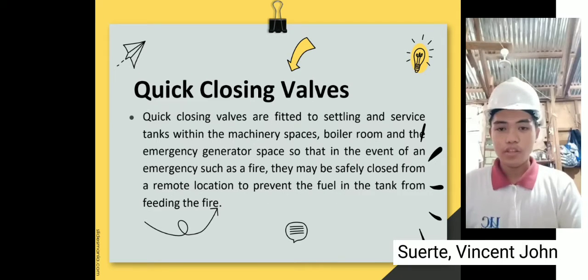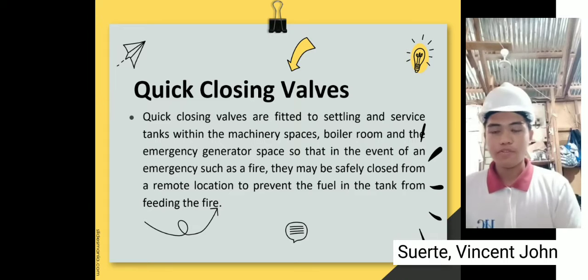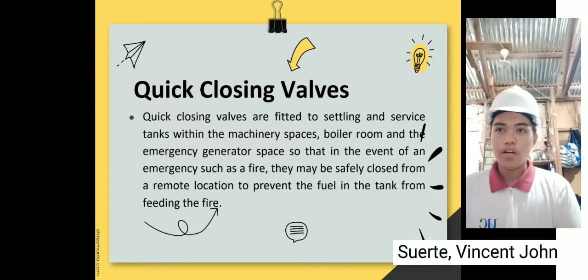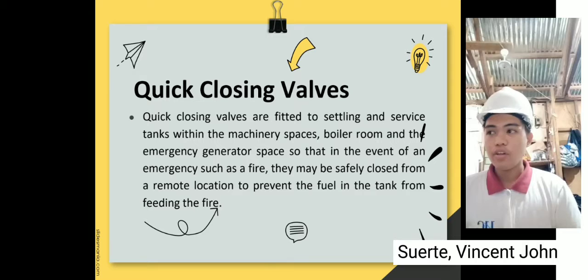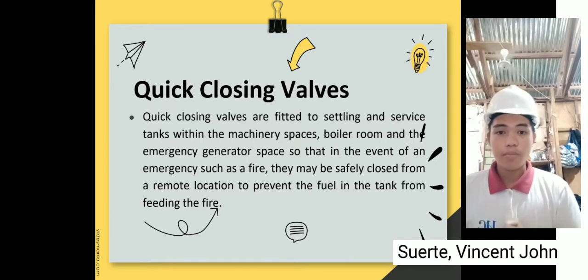The next is the quick closing valves. These are fitted to settling tanks and service tanks within the machinery space, boiler room, and emergency generator space, so that in the event of an emergency such as fire, they may be safely closed from a remote location to prevent the fuel in the tank from feeding the fire.